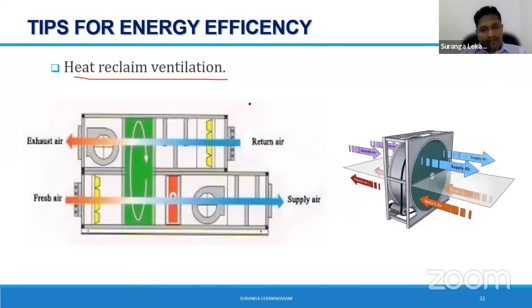Then heat reclaim ventilation. Yes, this will also add some benefits in terms of energy. If you have continuous exhaust from your conditioned space, rather than just dumping that exhaust, you can use that exhaust air to cool your fresh air to a certain level, right? That is called heat reclaim ventilation. You can think, let's say, of a hotel building where the guest room toilets are continuously discharging, or rather extracting. That air is more or less at room temperature, 24, 25, maximum 26. So rather than dumping it back, you can use a proper system.